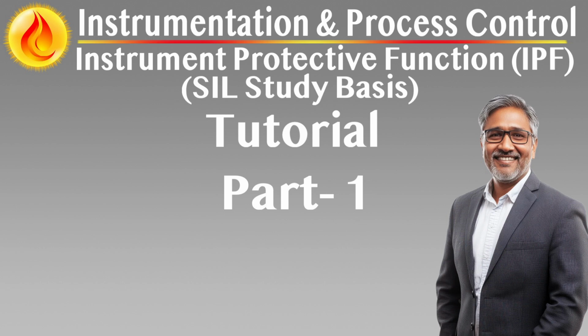SIL 3, PFDAVG 10^-3 to 10^-4. Typical risk reduction factor 1000 to 10,000. SIL 4, rarely used in process industries. PFDAVG 10^-4 to 10^-5. Typical 10,000 to 100,000. Verification and documentation requirements as defined.